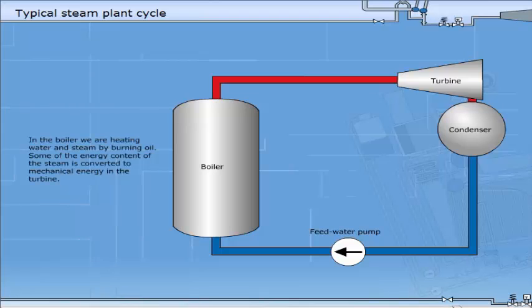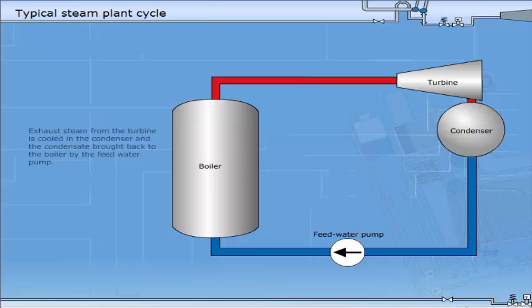In the boiler, we are heating water and steam by burning oil. Some of the energy content of the steam is converted to mechanical energy in the turbine. Exhaust steam from the turbine is cooled in the condenser, and the condensate brought back to the boiler by the feed water pump. The series of processes involved is called a steam cycle.